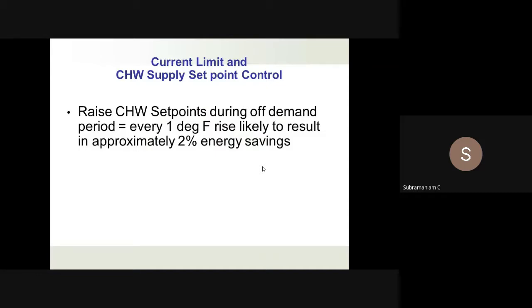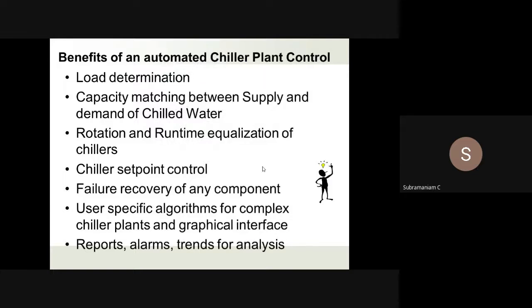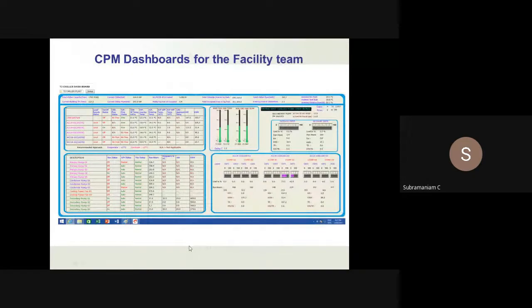And if you raise the chilled water leaving set point, you get an energy saving there. So these are the advantages of chiller plant control. It determines the load, capacity matching, runtime equalization, failure recovery, and we can do complex algorithms. Reports are available, and chiller dashboards we can see from the BMS. How exactly we want to do it, we can decide from there.